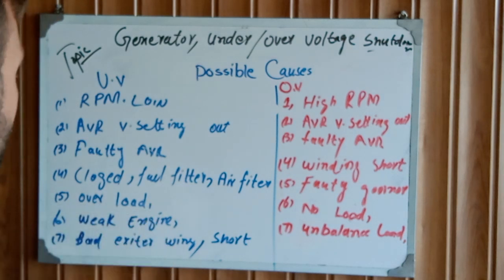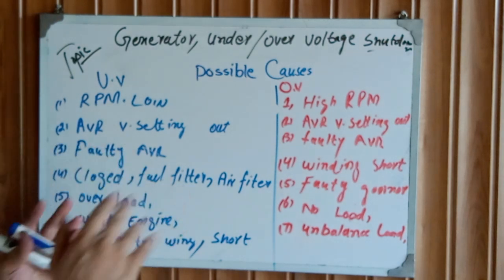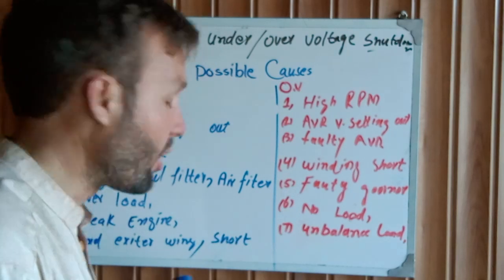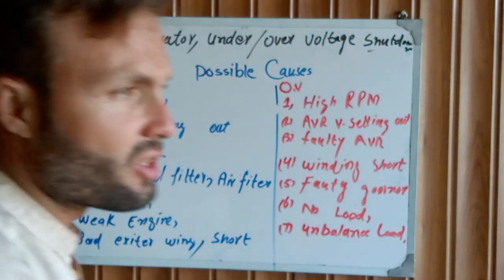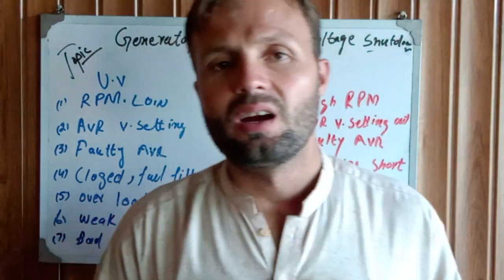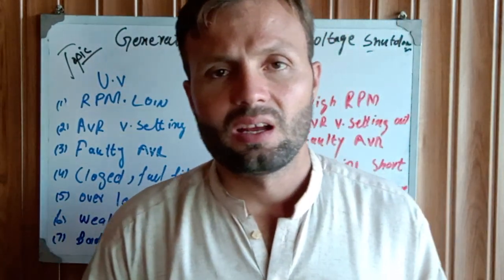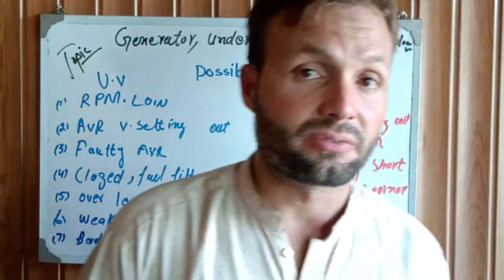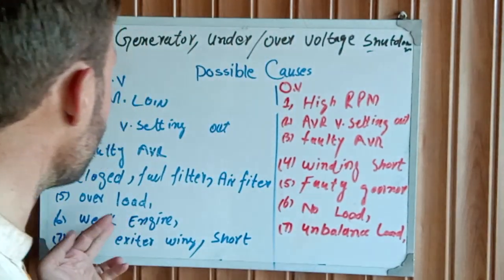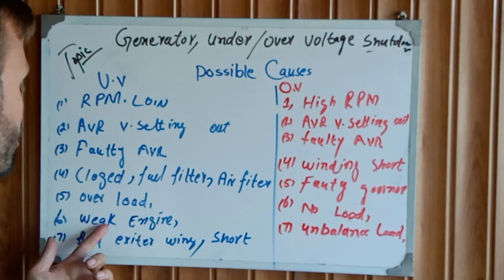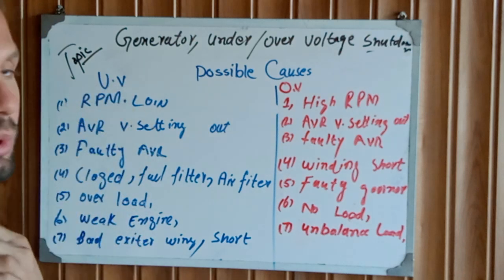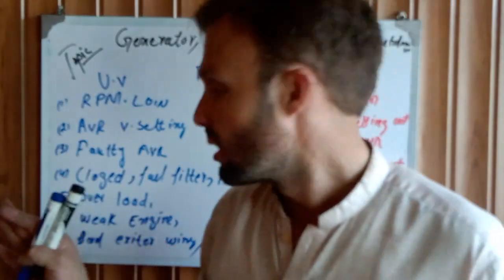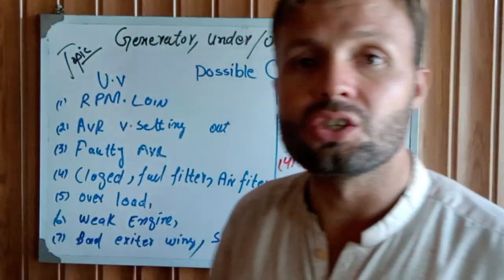Please note the specific load capacity of the engine and how much it can carry. Another cause is a weak engine. If the engine piston rings are worn out and engine compression is low, the engine cannot make enough power — that means under voltage. If your engine has too much blow-by and oil burning, that means your engine is weak, which will also cause under voltage.